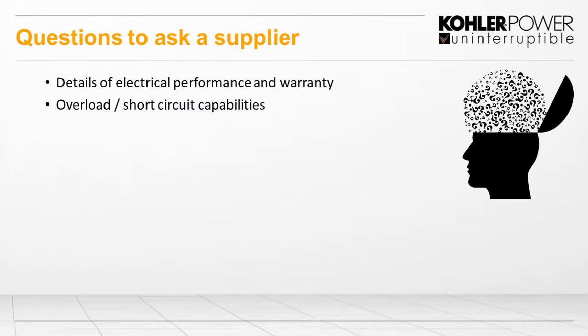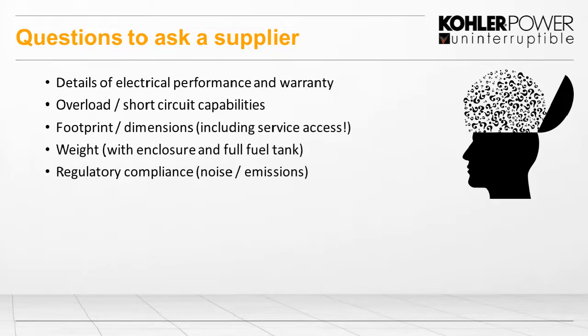So what we're going to do is talk to the suppliers, make sure we understand the performance of the generator, what kind of warranties it has, what the overload, short circuit, the actual step loading, things like this. And then we can determine the footprints depending on the fuel and actual silencers and things like that, and how heavy this is going to be, with the fuel as well, and make sure that you can comply with the regulations around all the noise and emissions, which in some places are also very critical as well.